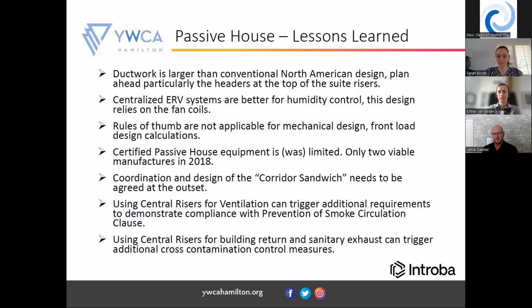There are also code requirements about centralizing ERVs and having smoke dampers to prevent smoke from going between suites. You have to be careful with that and make sure it's addressed in the design and coordinated with the electrical team. Cross-contamination also came up in our permit comments, about how we're controlling that at the back at the ERVs, so it's something to watch out for. We did revise it and the strategy went forward as planned, but it was a comment that came back and maybe wasn't clear enough in our original documents.